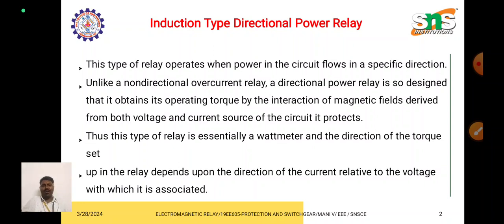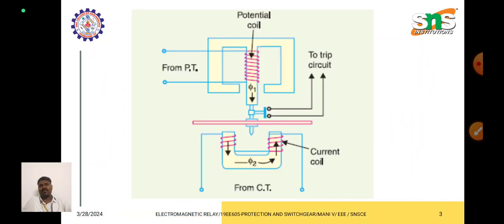Unlike a non-directional overcurrent relay, a directional power relay is designed so that it obtains its operating torque by the interaction of magnetic fields, which are derived from both the voltage and current sources of the circuit. This type of relay is essentially a wattmeter, and the direction of the torque that is set up depends on the direction of current relative to the voltage. So this is the schematic diagram.